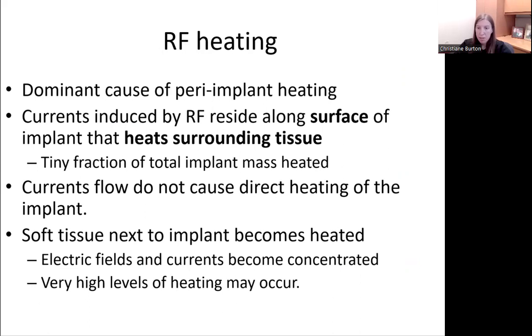Those swirling eddy currents induced by the RF fields do not penetrate to the center of the metallic implant, but instead reside almost entirely along its surface. RF-induced currents flow through a tiny fraction of the total implant mass at its surface and do not cause direct heating to the implant. In the soft tissues immediately adjacent to the implant, however, electric fields and currents become concentrated and very high levels of heating can occur.